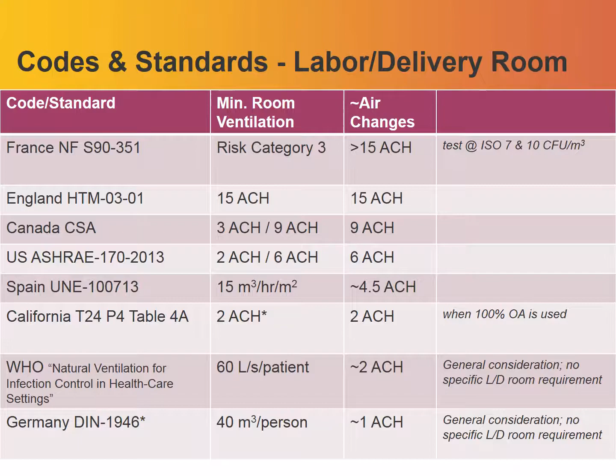When I give this presentation, I talk about the labor and delivery room example on purpose, rather than operating rooms and isolation rooms. This is our Fontana Medical Center, a 1.6 million square foot campus. We have ORs, isolation rooms, and critical spaces making up about 200,000 square feet. That's less than 15%, meaning there are 1.4 million square feet of non-critical spaces at this campus.